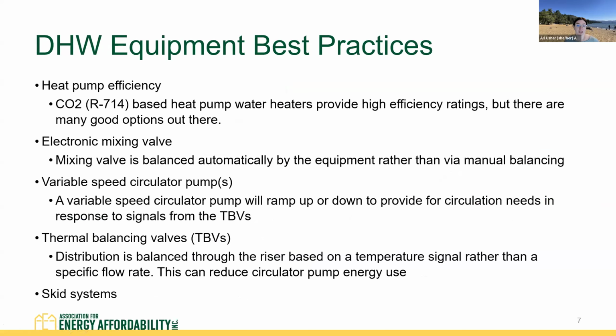But when we're thinking about equipment and speccing the equipment, there's a couple of things to consider in terms of energy efficiency. So the first thing is the heat pump efficiency itself. In California, a central heat pump water heater needs to be certified to the Energy Commission as JA14 compliant. So there is a limited list of heat pumps that can be installed in California, but there's a lot of great options on that list. One thing to call out is systems using CO2 as a refrigerant have really good efficiency ratings because they can operate very well down to even low ambient temperatures. But there's a lot of good options out there.